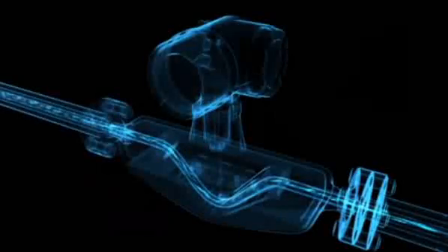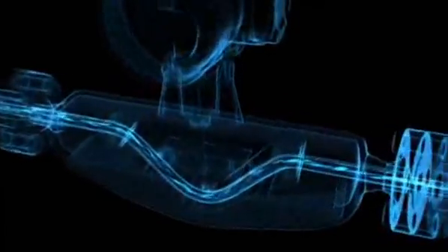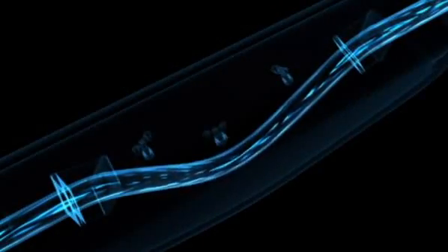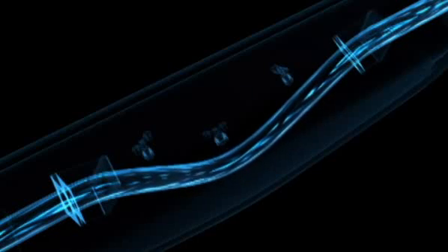Here's how it works. The flow meter consists of a tube or series of tubes that are set to oscillating. If there's no flow, the tube oscillates uniformly, and sensors at the inlet and outlet of the tube are used to sense the oscillation very precisely. When fluid starts to flow in the tube, there's a twist imparted to the tube. This application of the Coriolis effect causes the sensors to pick up the phase shift that is proportional to the mass of fluid or gas in the tube. The higher the throughput, the greater the shift, which is directly proportional to the mass flow in the tube.